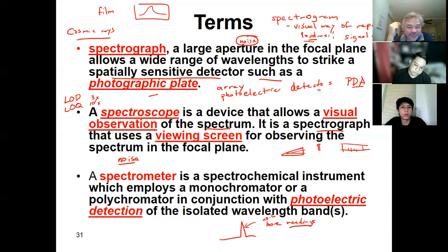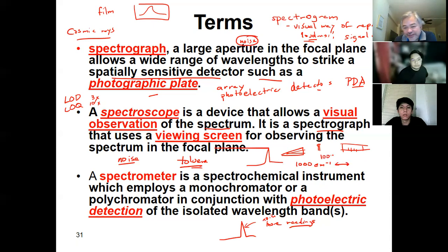But what if your own signal shifts on its own? I remember, because what we usually do is we always get the reading of the toluene. The toluene will give us a sharp peak around 1000 wave number. After 5 years of working in the lab, we found out that there's a shift. Let's say in 2011, it's around 1003, and then in 2018, it's around 1008.